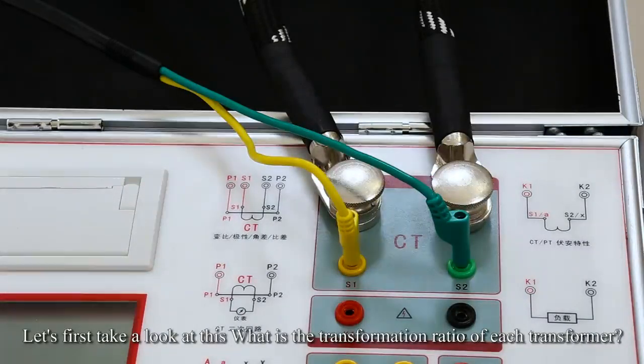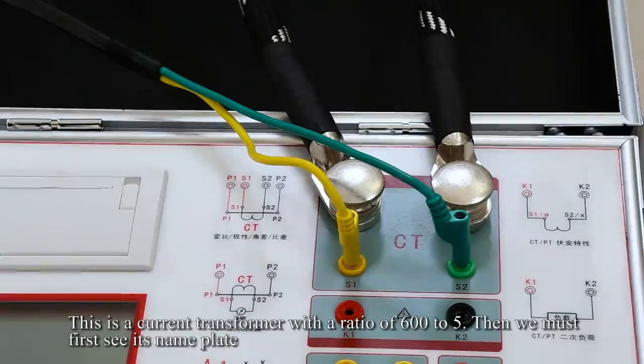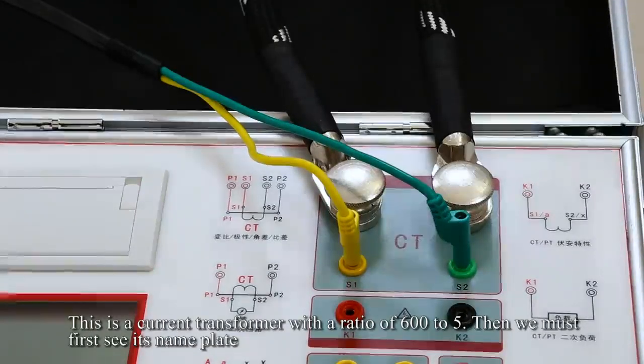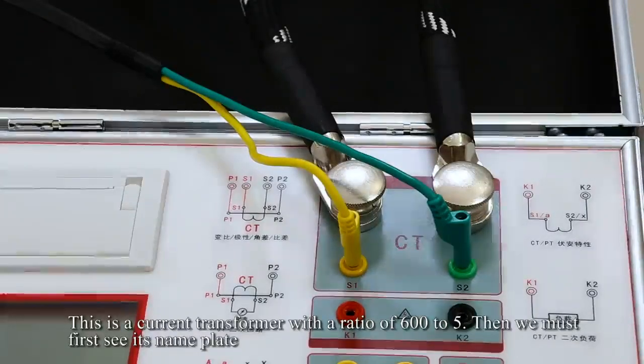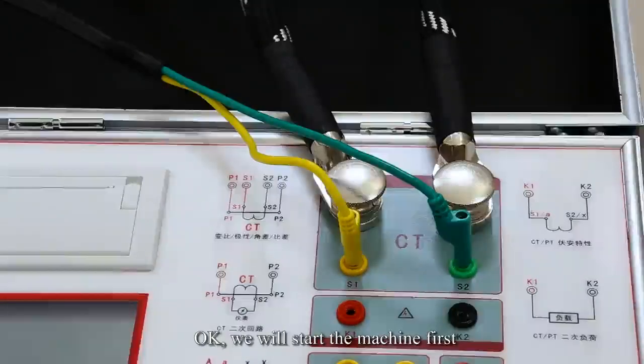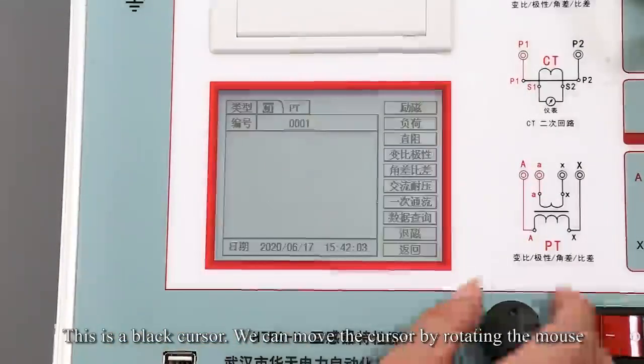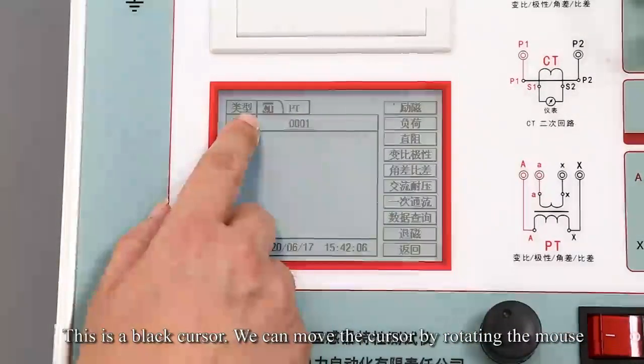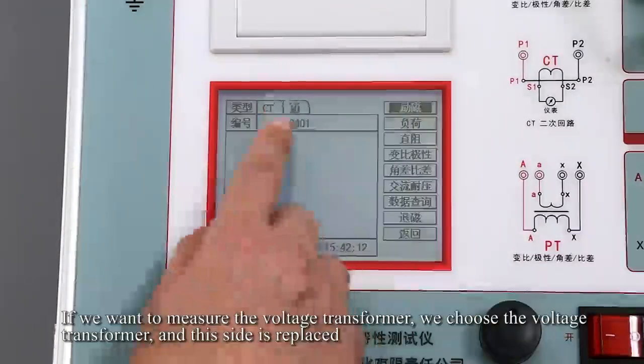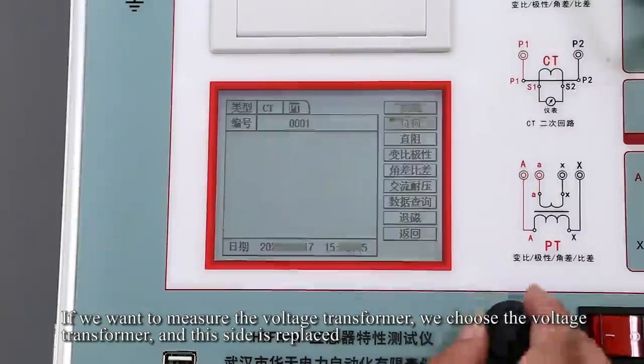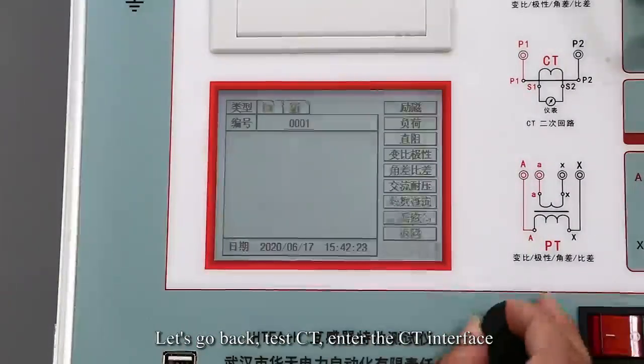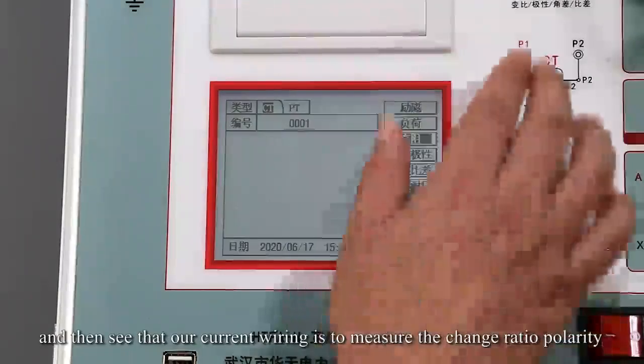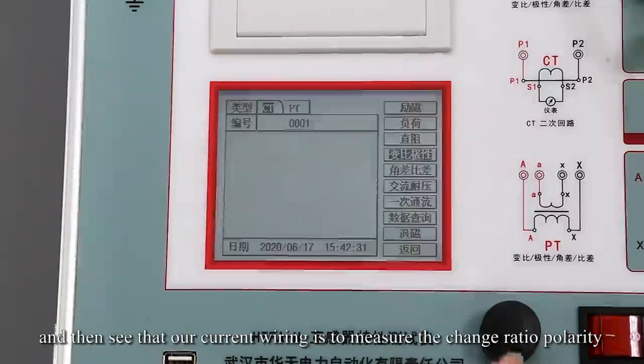Let's first take a look at the transformation ratio of this transformer. This is a current transformer with a ratio of 600 to 5, and we must first check its nameplate. Okay, we start the machine and enter the main interface. There is a black cursor, and we can move the cursor by rotating the knob. The type we are measuring is CT. If we want to measure the voltage transformer, we choose the voltage transformer instead. Let's go back and choose Test CT.